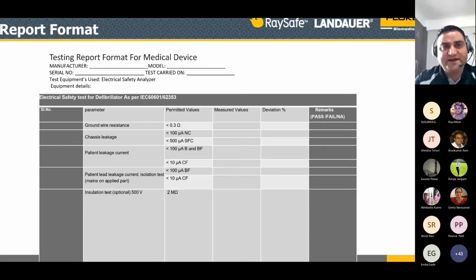This is a report format which normally shows these permitted values. They are the parameters. Ground wire resistance should be less than 0.3 ohms. Chassis leakage, like as I said, enclosures, touch currents and all, should be less than 100 microamperes. NC, what I was discussing, NC is normal condition. And less than 500 microamperes is SFC, single fault condition. As I said, if your neutral is not at a neutral place, it is in phase, then it is a single fault condition. You are making a single fault condition, then you can have this kind of permissible limit.